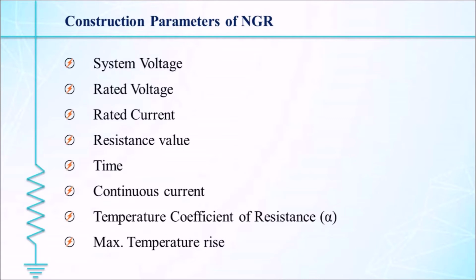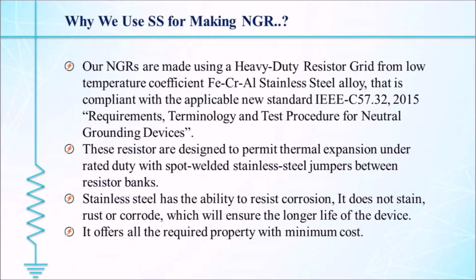In case of NGR, rated voltage and current depend on the device to be protected. For NGR, we need a material with positive temperature coefficient. The value of electrical resistance is decided by the customer according to their requirements. As per IEEE rules of designing NGR, maximum temperature rise is 760 degrees Celsius and rated time of operation is within 10 seconds. Now have a look at why we use stainless steel only for making NGR.